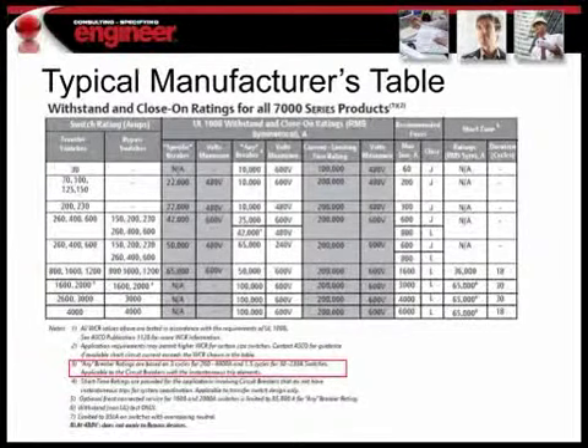The other important point to note, finally, is notice how large the withstand and close-on ratings are when you apply current limiting fuses. The current limiting effect of a fuse located ahead of a transfer switch works to limit the available fault current that passes through that switch. So when you perform the UL test, you're able to provide up to 200,000 amps of fault current at the source, and the transfer switch will see that value significantly less than that 200,000 because of the current limiting effect of that fuse. I'll cover some cautions a little bit later in the presentation about why you need to be careful when applying current limiting fuses ahead of transfer switches.